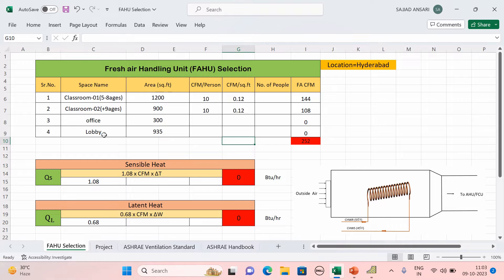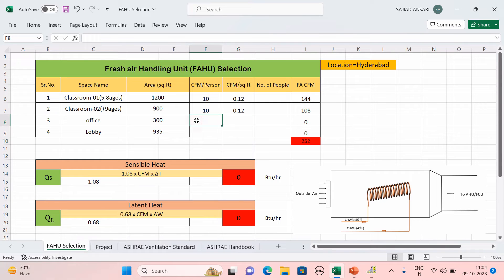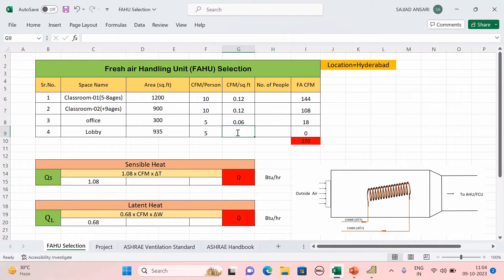Now calculate the same values for Office and Lobby. In ASHRAE for Office Space: CFM per person is 5 and CFM per square feet is 0.06. For Lobby, Main Entry Lobby is listed: CFM per person is 5 and CFM per square feet is 0.06. So for both Office and Lobby, CFM per person = 5, CFM per sq ft = 0.06.